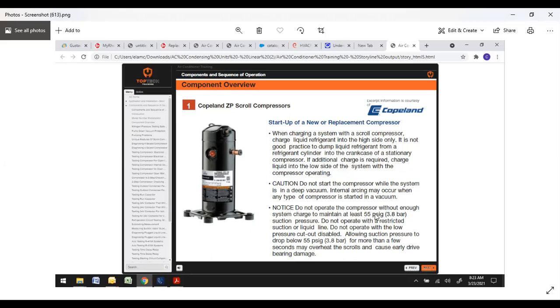And do not operate a compressor without enough system charge to maintain at least 55 psig. Do not operate with a restricted suction or liquid line. Do not operate with a low pressure cutout disabled. And allowing suction pressure to drop below 55 for more than a few seconds may overheat the scrolls and cause early bearing damage.